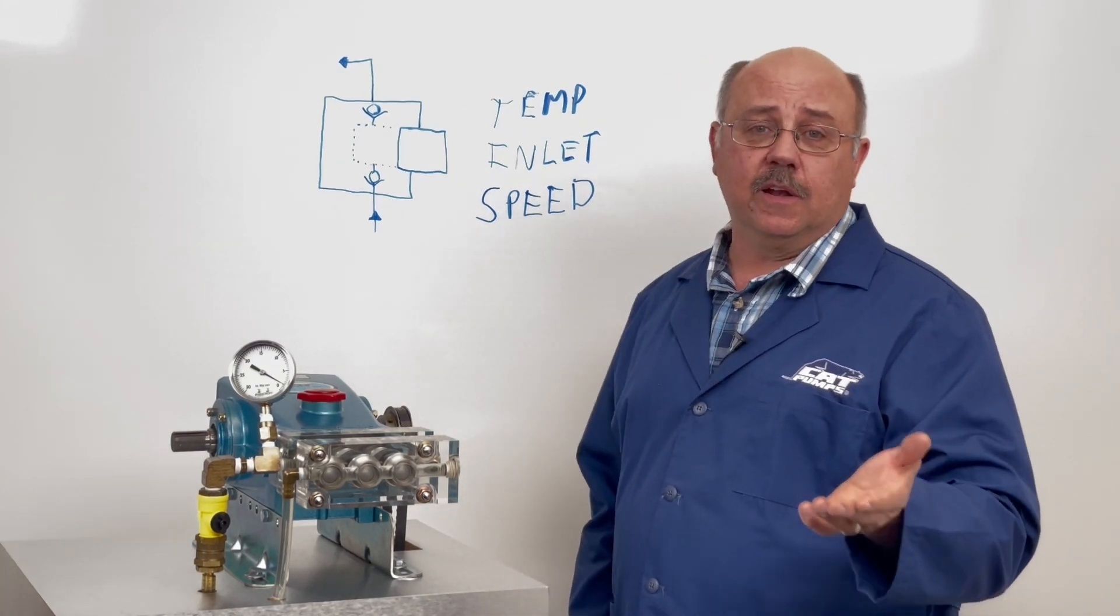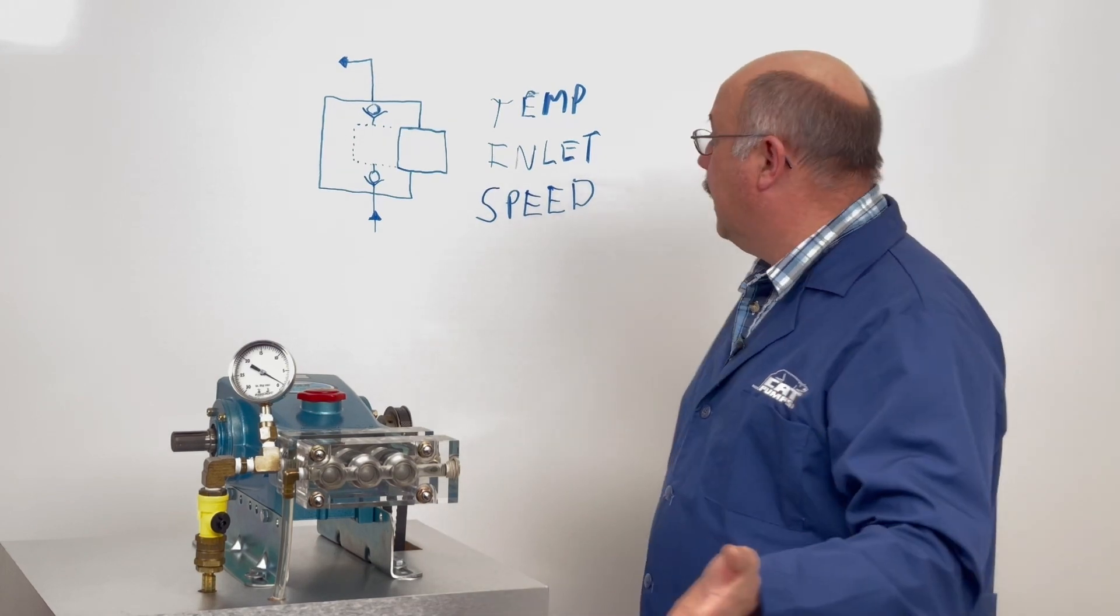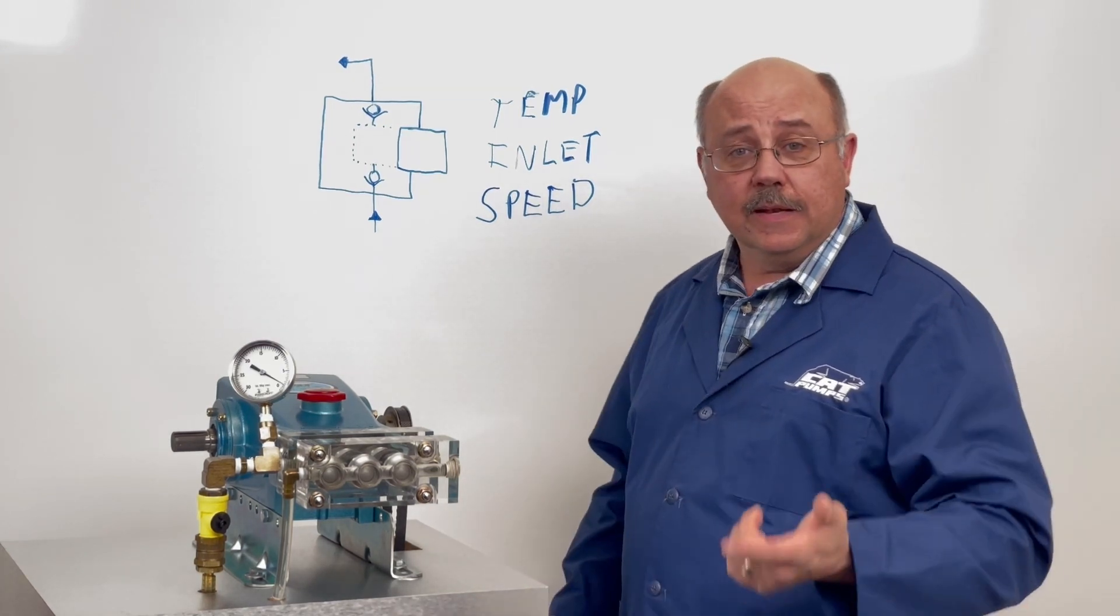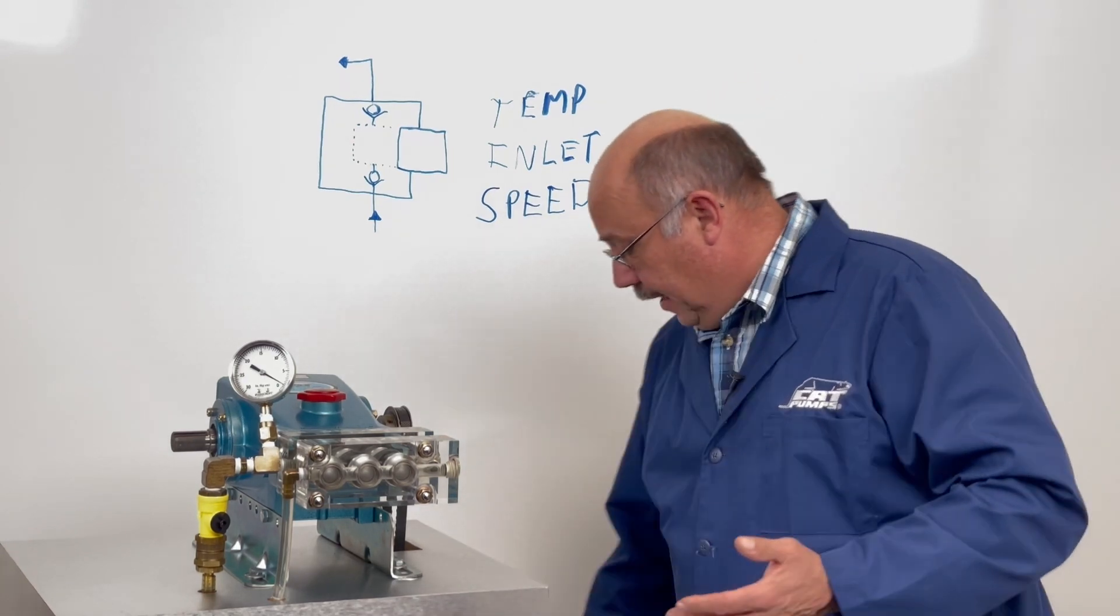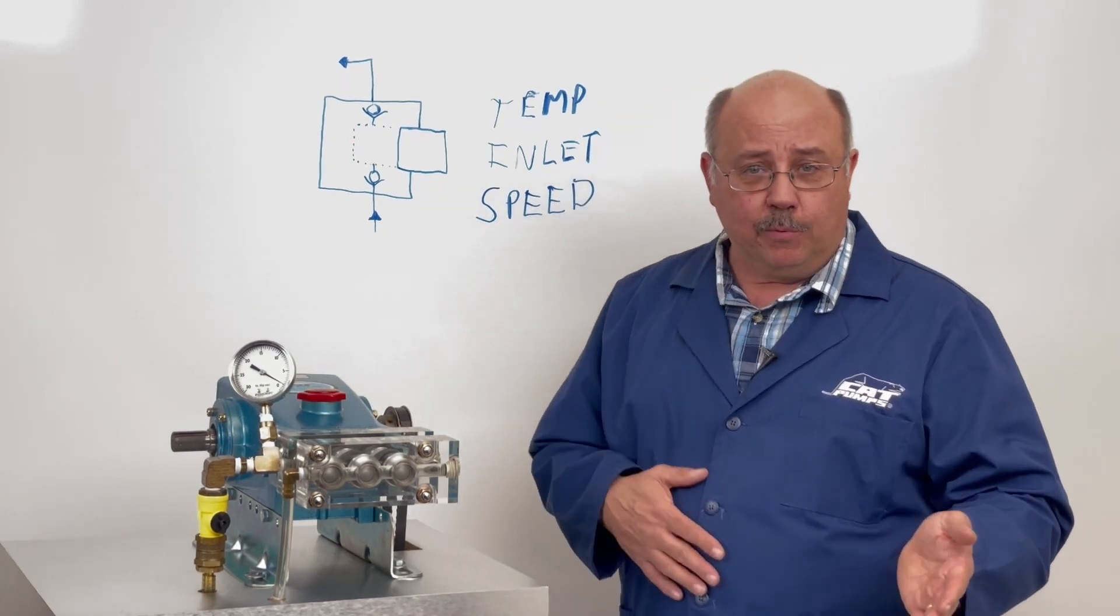And so those are the things we need to consider to avoid cavitation. The temperature of the water, the inlet conditions, and the speed of the pump. With that, we can move into the actual operation on a pump.